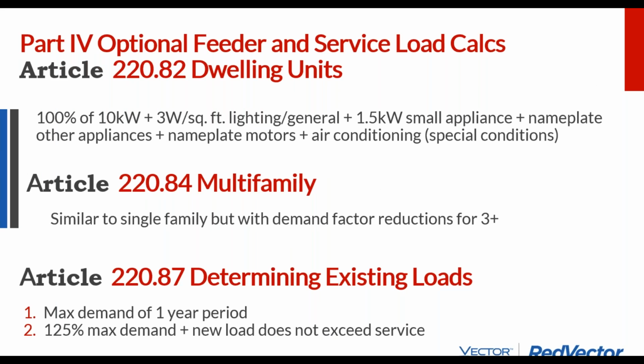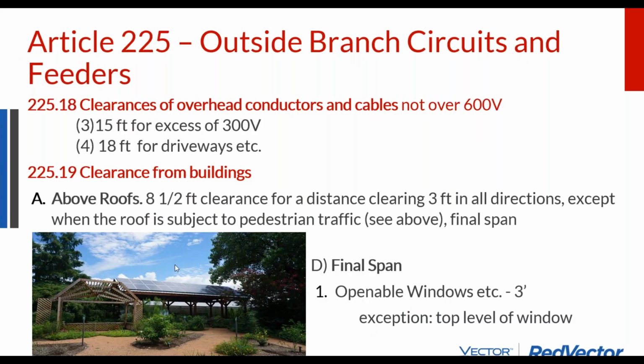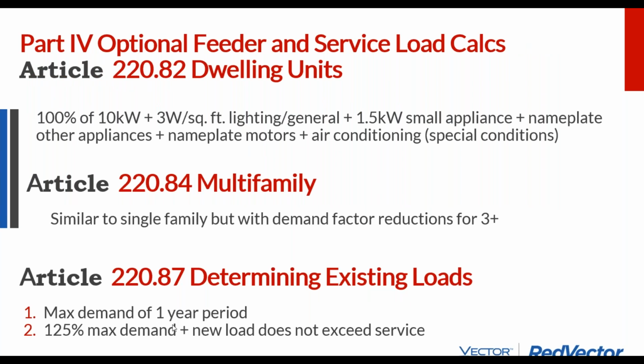In the interest of time, I'm going to skip over some of these load factors. Basically, if you have an existing load, you're allowed to use your maximum load over a 1-year period. If you have more than 1 year of demand data, then that's probably best.